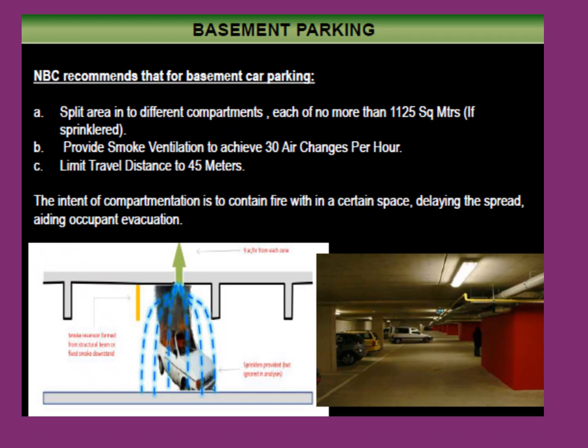Friends, now we'll discuss the basement parking area. NBC recommends that for basement car parking, one splits the area into different compartments, each of not more than 1125 square meter if sprinklers are provided. Second, provide smoke ventilation to achieve 30 air changes per hour. The third, limit travel distance to 45 meters. The intent of compartmentation is to contain fire within a certain space, delaying the spread and aiding evacuation.